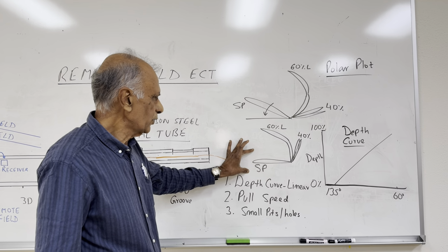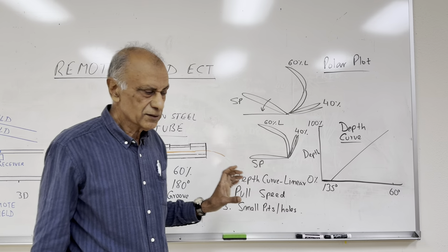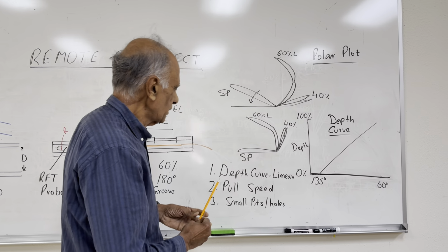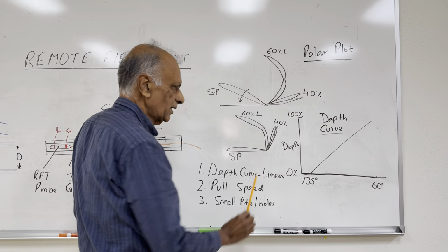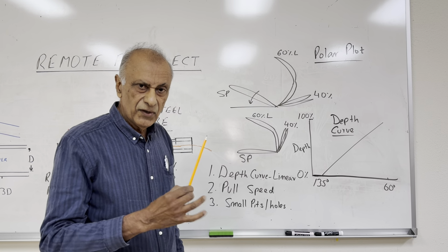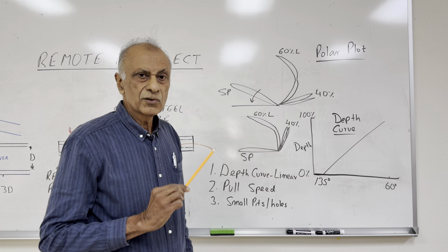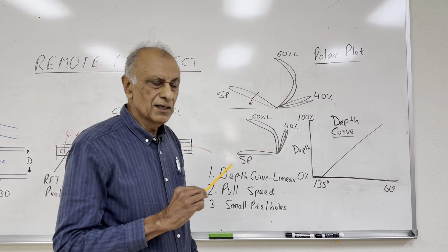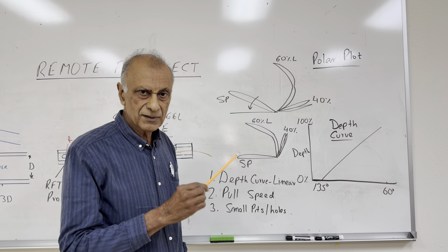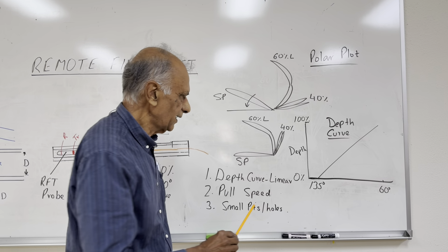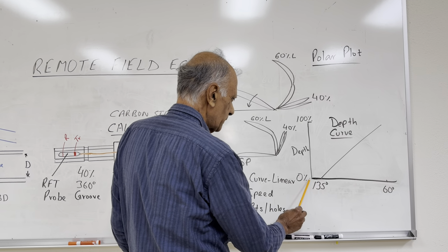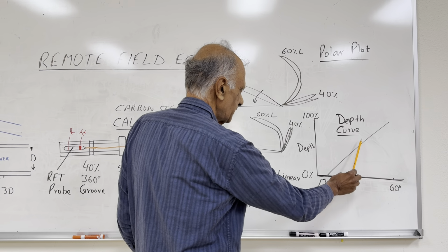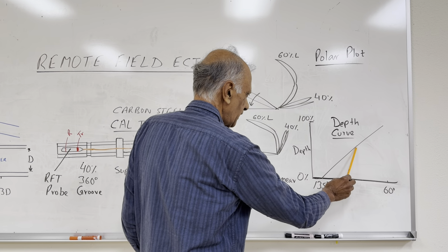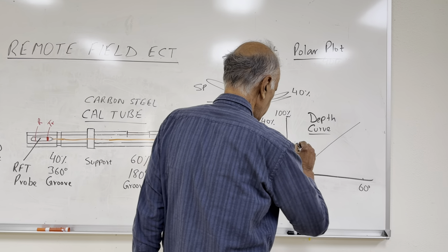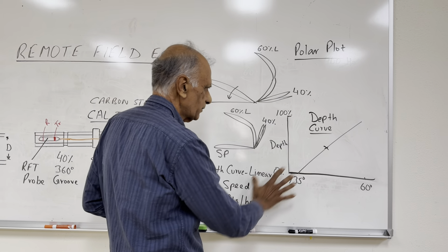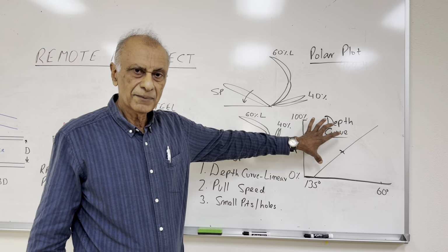Once you have this support plate horizontal, then the next step is to make the depth curve. The depth curve, we will make it on the short flaw, which is like 40%, and when you make the depth curve, it's a linear curve. Like I said, a remote field phase change is linear. So all you need is a single point to make the depth curve. You don't need, like in conventional eddy current, remember we made the depth curve on 5 different points, like 20%, 40, 60, like that. Here all you need is a single point, and then it makes a depth curve where 135 degrees is 0%, and all you do is pick up either the 40% or the 60%, which is right here, and get the phase, and you pick one point, and it will make the linear depth curve. So this depth curve will be used to estimate the depth of the flaw.